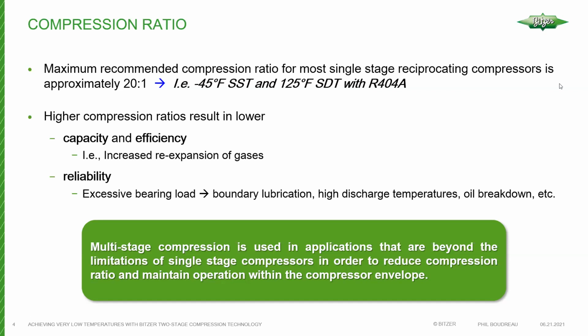Reliability also, when you're running very high compression ratios, places additional load on the bearings, creates lubrication challenges, as I mentioned before, high discharge temperatures leading to carbonization of the oil, oil breakdown, what have you. So obviously we want to avoid these at all costs. So in these situations where compression ratio is going to be high, multi-stage will be used. You can use separate compressors, you can use multi-stage systems such as boosters and cascades and auto cascades and what have you. In this case, we're using an internally compounded compressor, one compressor that's been reconfigured for a two-stage setup.